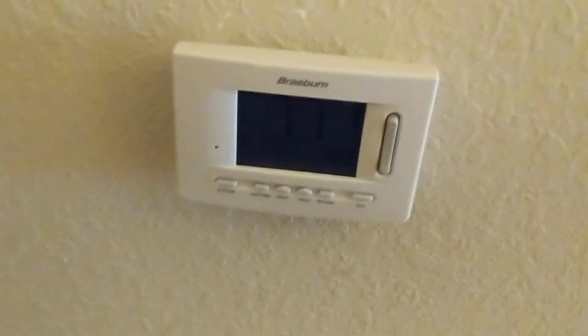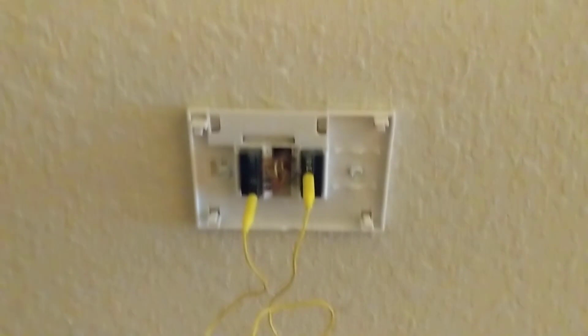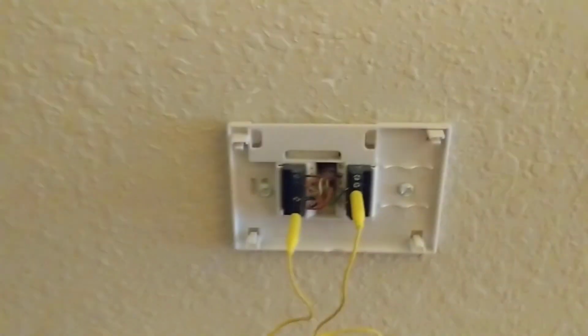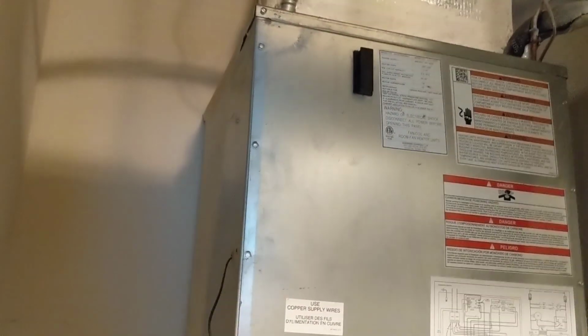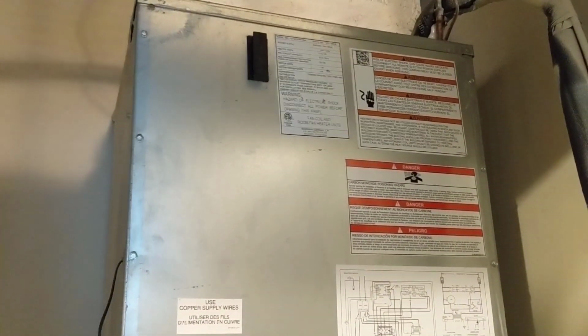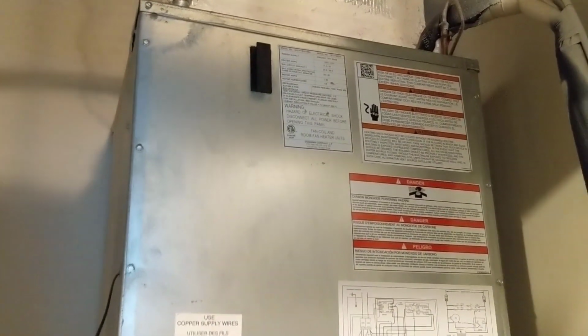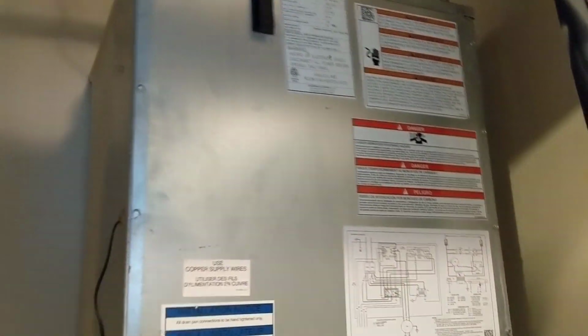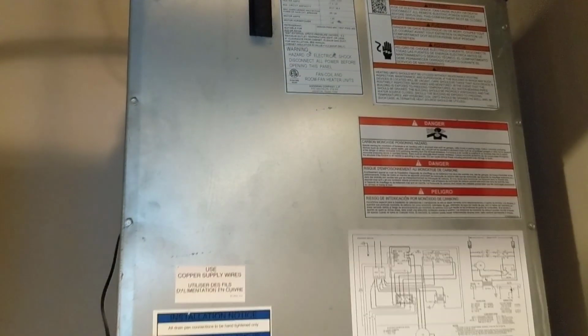But I guess we'll see if it's the thermostat. We'll start there, jump it out and see what happens. I pulled the thermostat off, jumped it out, and still nothing. No indoor blower motor. So it looks like we'll pull the disconnect and the cover off, and we'll see if the little 3 amp fuse is blown, and we'll check the cap as well.